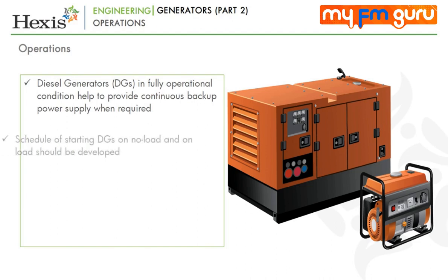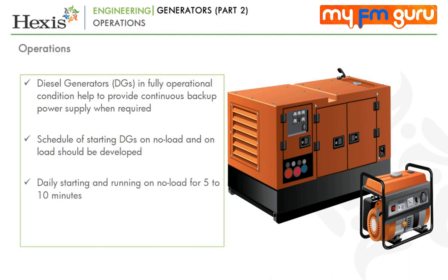Therefore, a schedule of starting DGs on no load and on load should be developed. Usually, a daily starting and running on no load for 5 to 10 minutes and a weekly running on load for 30 to 60 minutes is recommended.